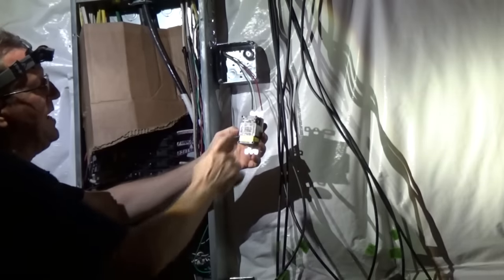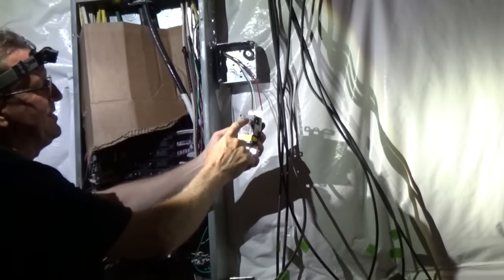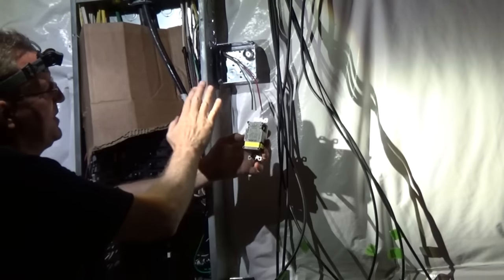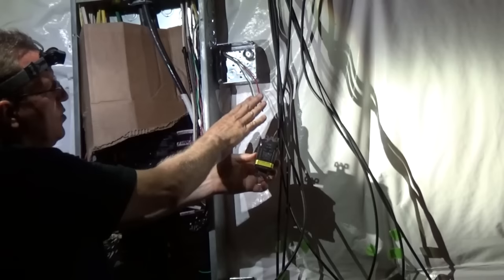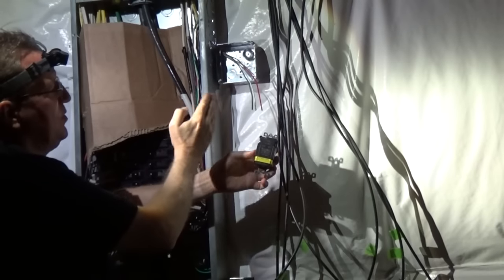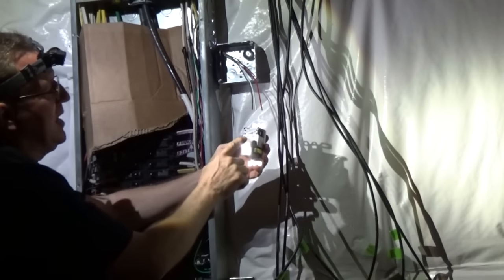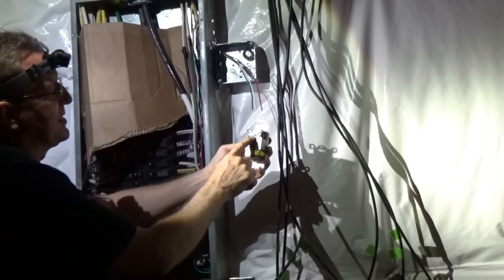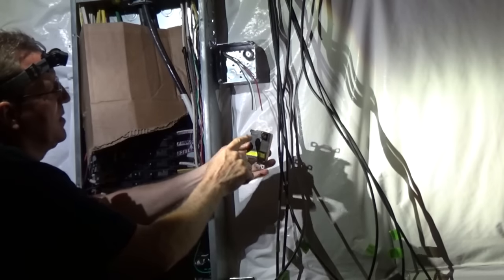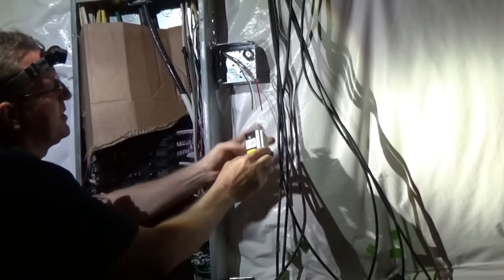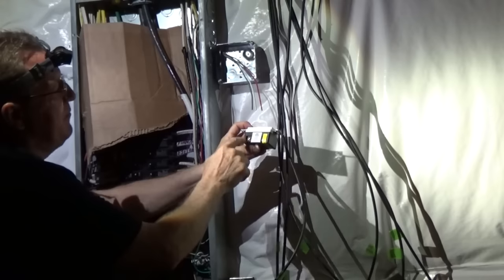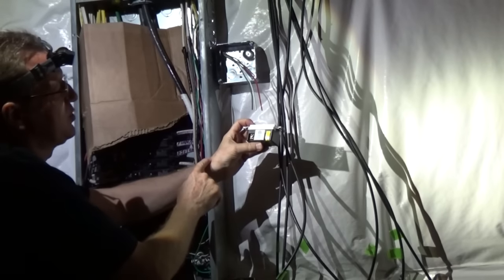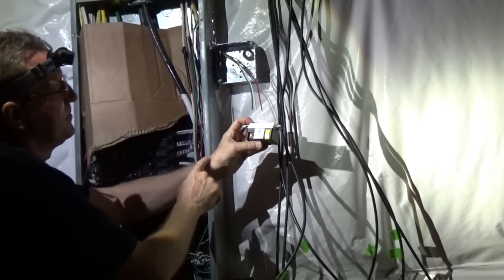On the GFCI, there's a line side and a load side. If you just have one group of wires, a hot, a neutral, and a ground, you're going to be connecting to the line side. So I'm going to strip about three-quarters of an inch of the insulation off and wrap it clockwise around my screw terminals.